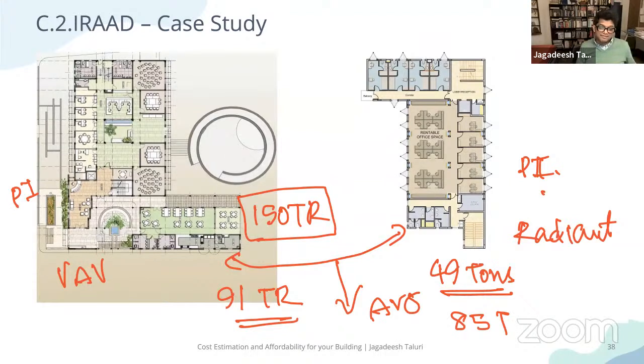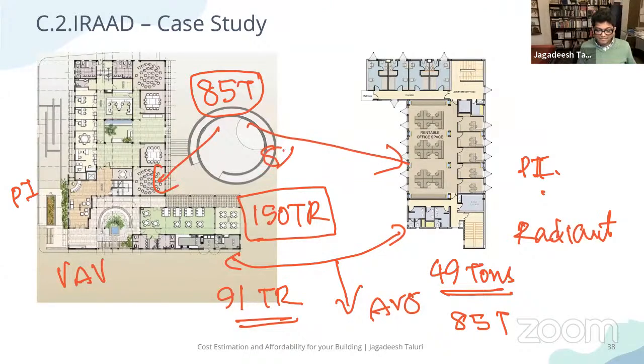So now what these people have done is, instead of buying a new 49 ton chiller, they bought an 85 ton chiller. With that, they were running both the buildings 80% of the time. They used the existing 150 ton chiller as a backup chiller, only for the 20% scenario when there was a requirement. A, they created redundancy. They have a safe backup. B, instead of running a 150 ton chiller plus a 49 ton chiller, they are basically making do with an 85 ton chiller, which was circulating to both. And they have also done it in a very smart manner.